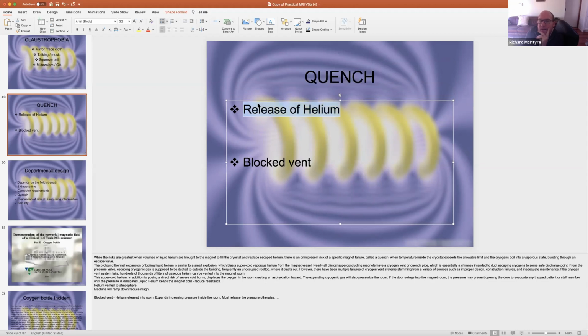We heat that up a tiny little bit, and then that liquid helium turns to gas, and it goes through a vent. There's a vent that's up here, goes out to the atmosphere, out of the machine. Unfortunately, the liquid helium, when it turns to gas, expands 700 times. That's a lot of gas. That's why we must have a working vent, and they must check that vent regularly to make sure that it's not blocked.